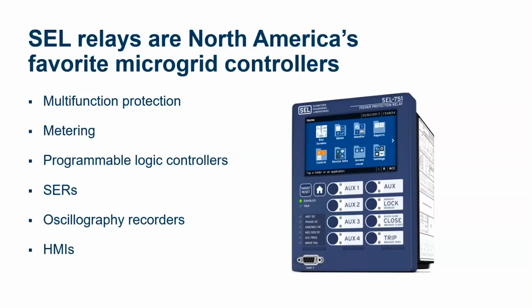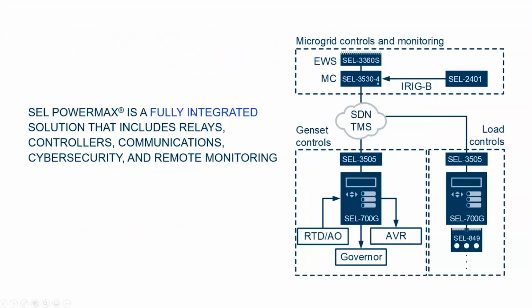With programming that can replace a PLC, you can replace a computer with expensive HMI software. You can replace a digital fault recorder, a high-speed data collection event, all with one relay. So it's a very economical, high value add choice that has made us the number one used device as a microgrid controller in North America. One SEL 751 relay may be sufficient for a single building service entrance job, a microgrid that might contain a battery, a photovoltaic, and a generator.